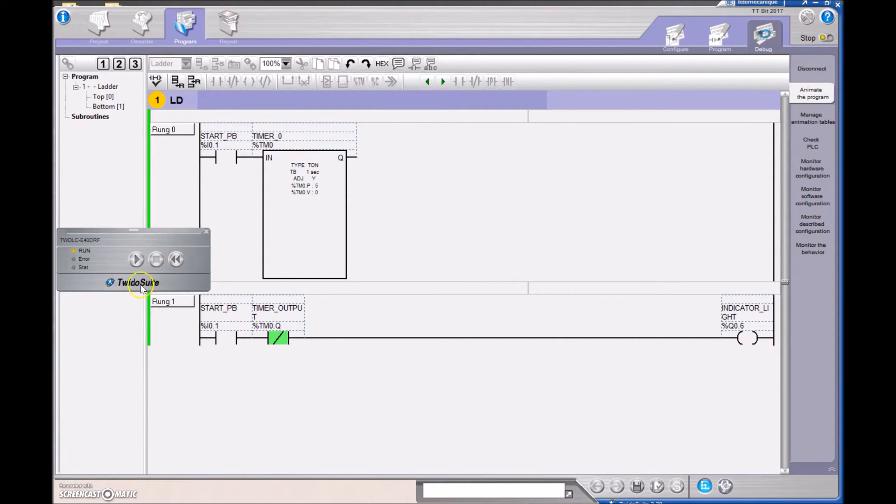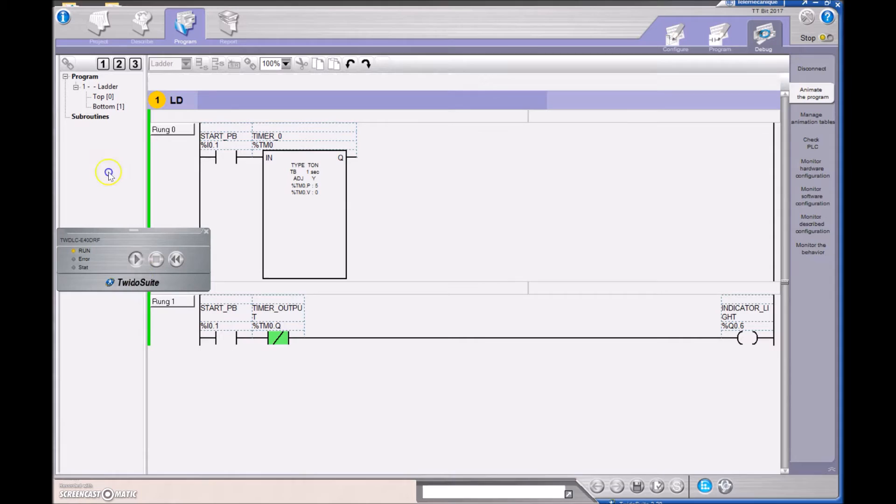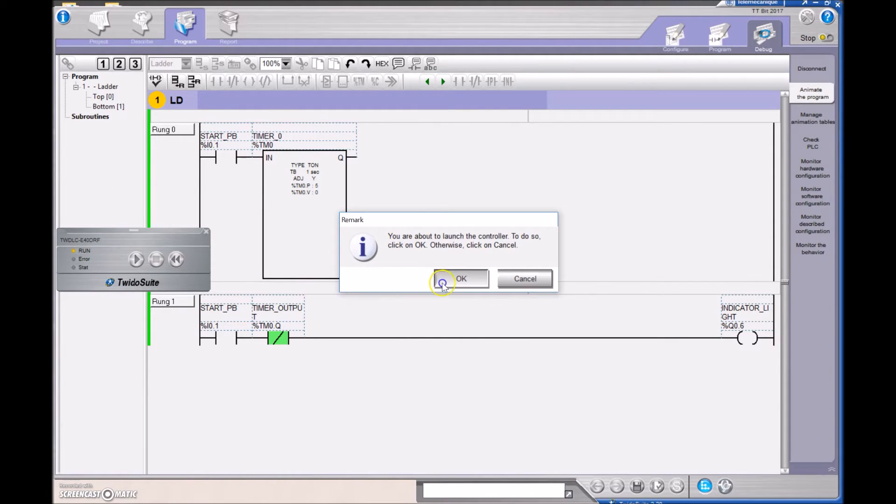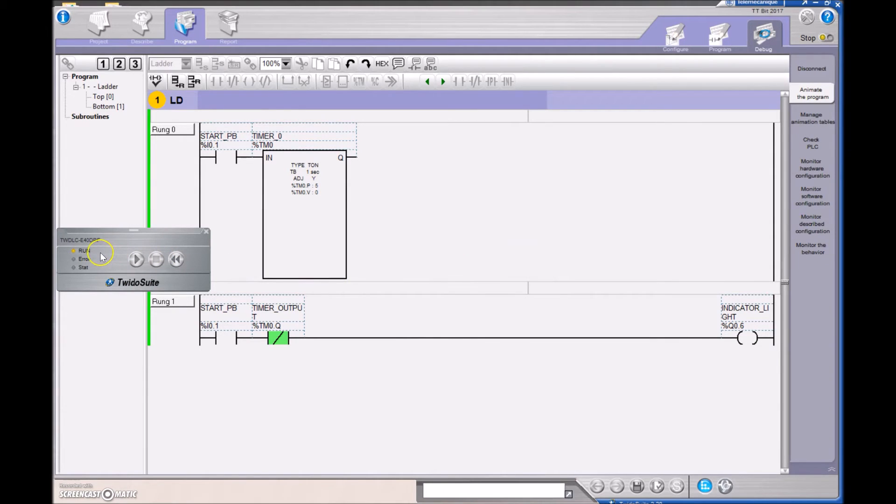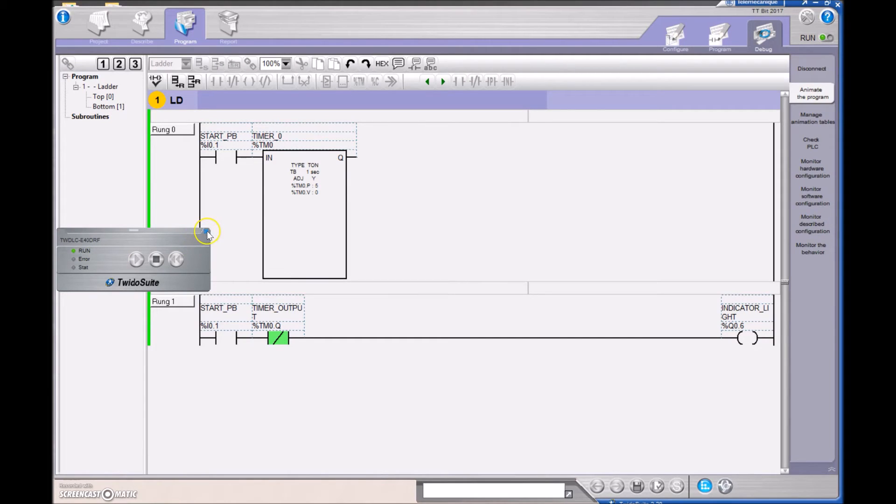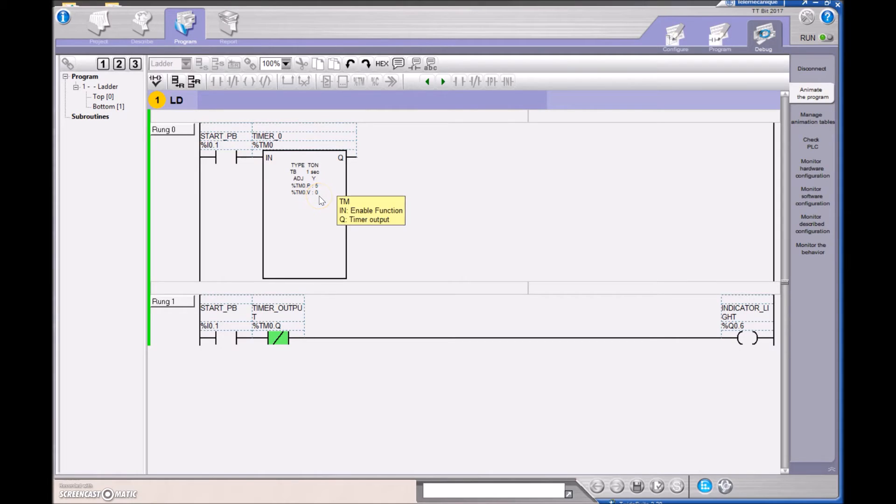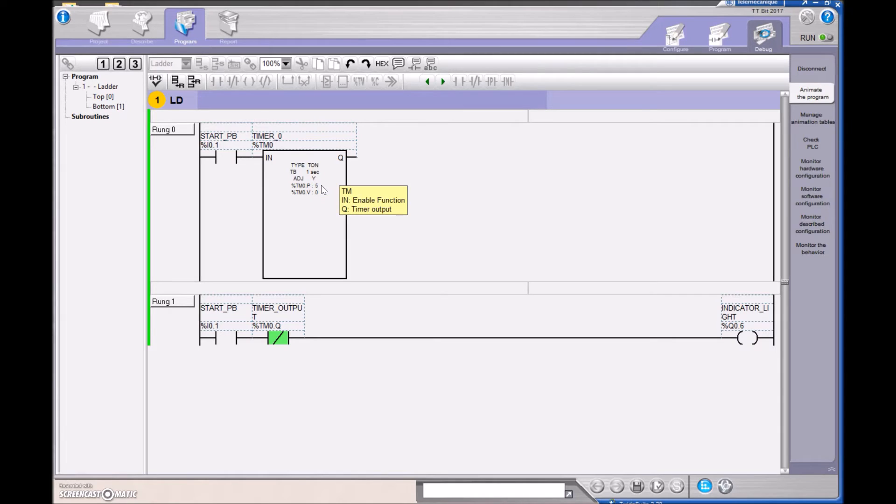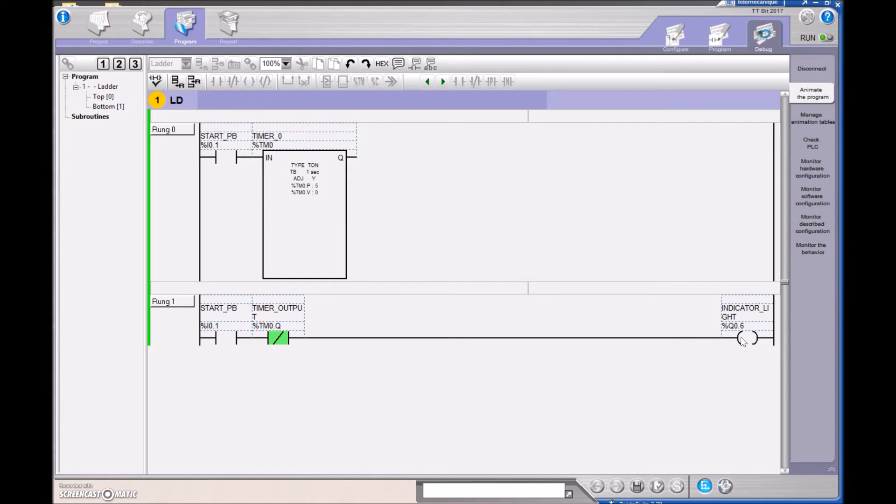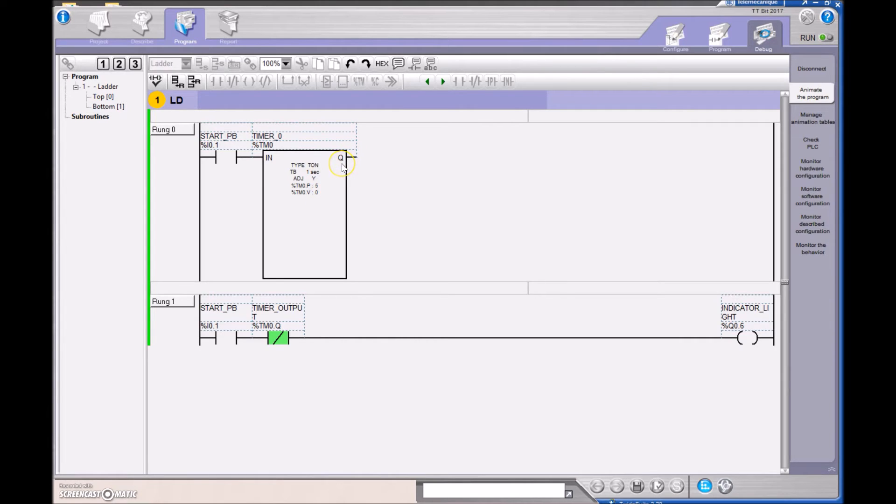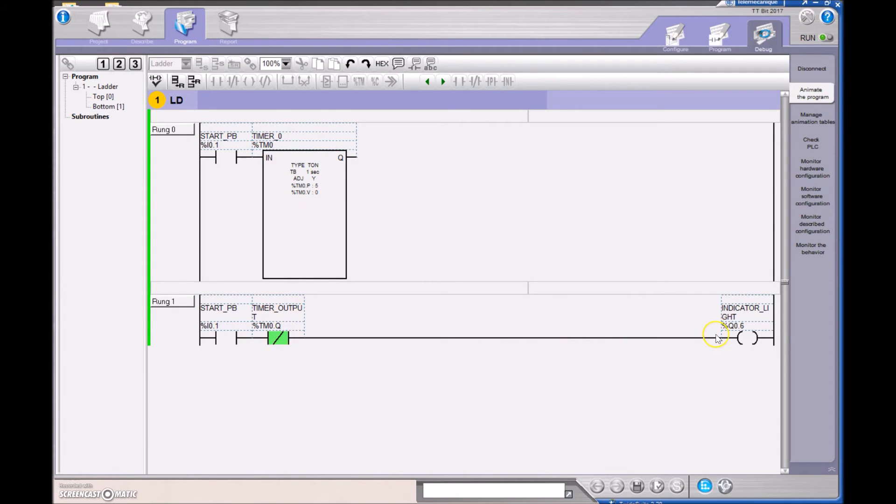Now that we're on this screen, we're going to hit Run. We're waiting for this green light to turn on. There we go. So we can minimize this. And now watch what happens. I'm going to hit the Start push button. That's going to start my timer incrementing. So right here is my accumulated value. It's going to start to increment up to a value of 5. And as it's incrementing up, this light is going to be on. So as soon as I hit the push button, the light is going to turn on. And the light will turn off when these two values are the same. The preset and the accumulated will be the same. This will be a 1. We're looking for it to be a 0. So as soon as this is a 1, this is not true. And the light will go out.